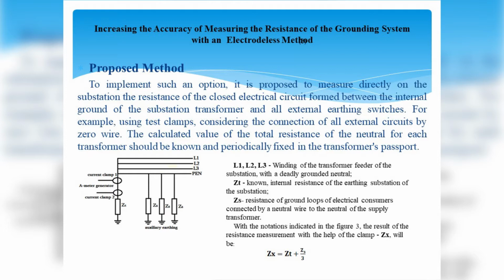If you know the intrinsic resistance of the earthing contour of the substation transformer when it is put into operation, then calculate the total earth resistance of the neutral and introduce it as an amendment to the result of the measurement of the ground loop being examined. To implement such an option, it is proposed to measure directly on the substation the resistance of the closed electrical circuit formed between the internal ground of the substation transformer and all external earthing switches. For example, using test clamps, considering the connection of all external circuits by zero wire, the calculated value of the total resistance of the neutral for each transformer should be known and periodically fixed in the transformer's passport.